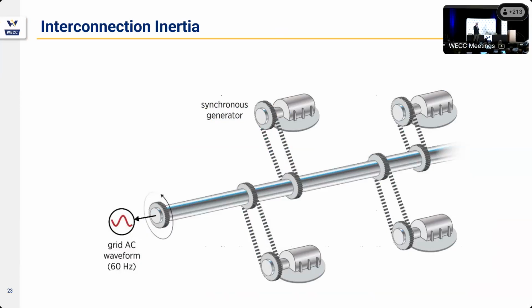Our power system is the same thing. The more inertia you have, basically the more mass that is rotating. So when you're trying to speed it up, it speeds up a lot slower, but the benefit is when you're trying to slow it down, it also tries to slow down much slower. Once you have a mass set in motion, it resists changing that speed. So when you connect a generator to the grid in any interconnection, all those synchronous machines are electrically acting as one, running the exact same speed. They might be running different RPMs based on how many poles the generators have, but proportionally, if a unit trips in Arizona, say Palo Verde trips off, every generator in the Western Interconnection slows down, because they're all electrically tied.